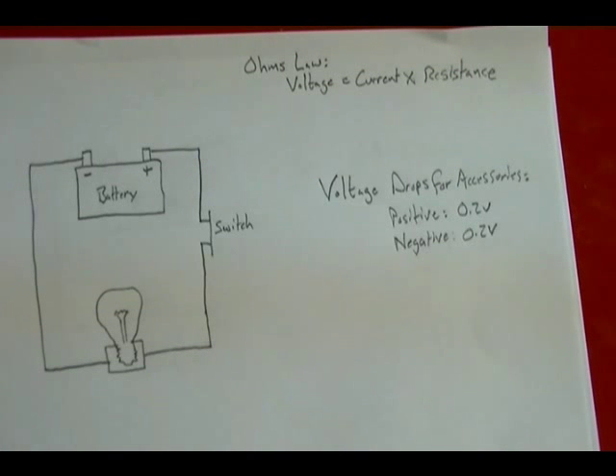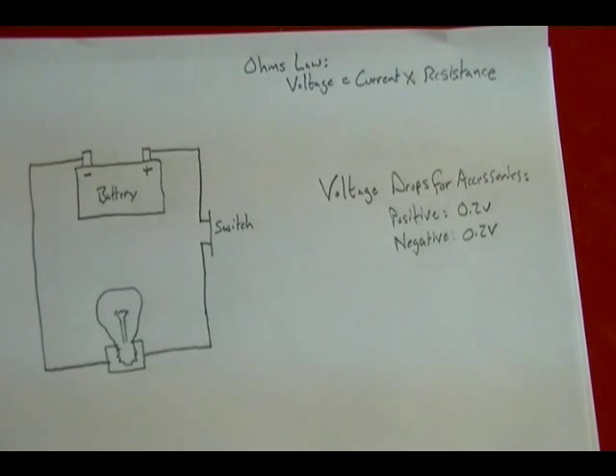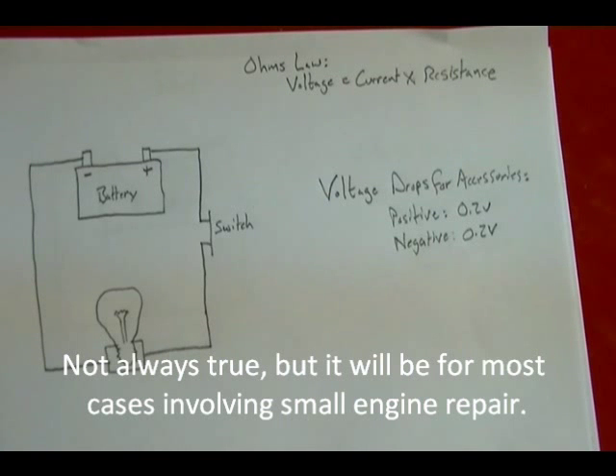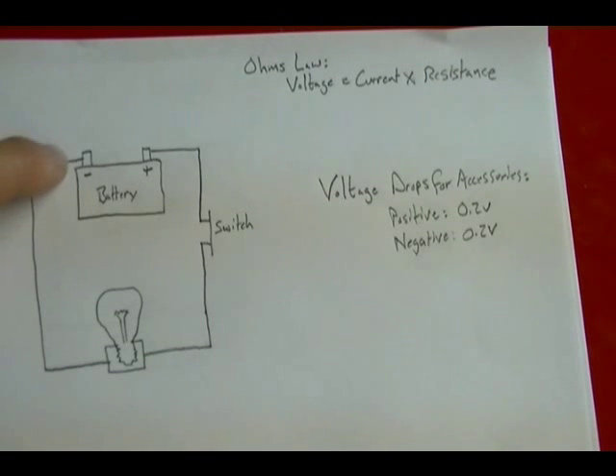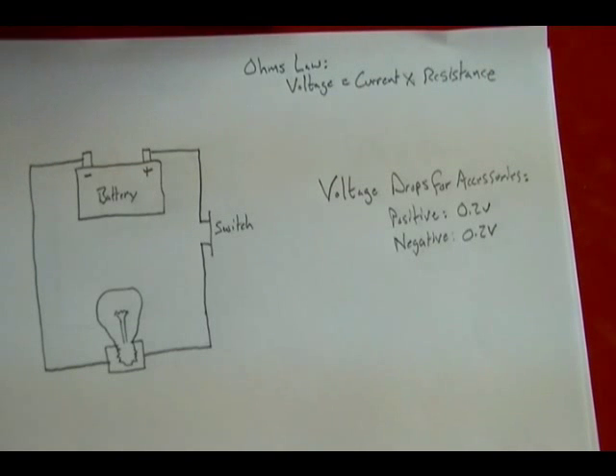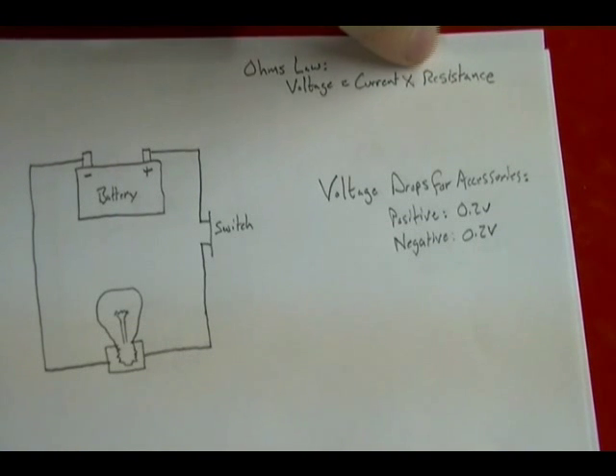When all the connection points are good and everything's new, you're going to have a very small voltage drop and it's going to be insignificant. But the older this circuit gets, the more corroded these connection points get, the more they loosen up over time, the more resistance it's going to create. And because of Ohm's law, when you have resistance and current flowing through whatever is creating that resistance, you're going to get voltage drops.